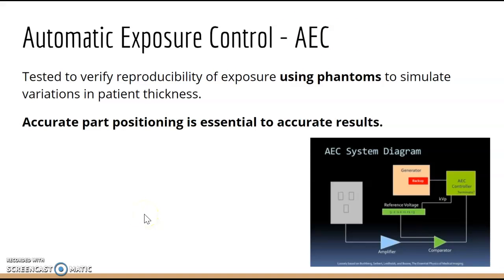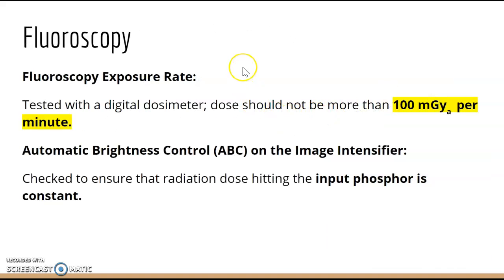Automatic Exposure Control — AEC — uses photo timing cells, and accurate part positioning over the photo cell is essential. For fluoroscopy, the exposure rate is tested with a digital dosimeter and the dose should not exceed 100 milligray per minute.